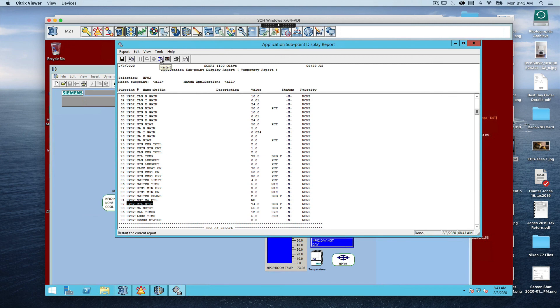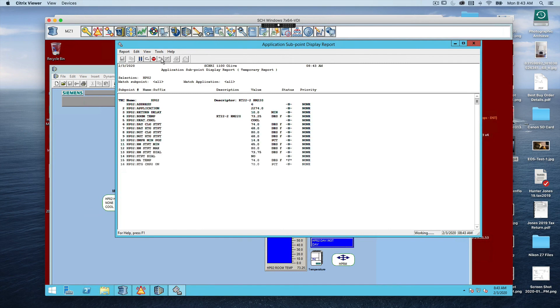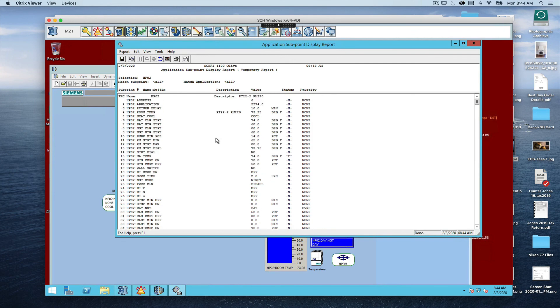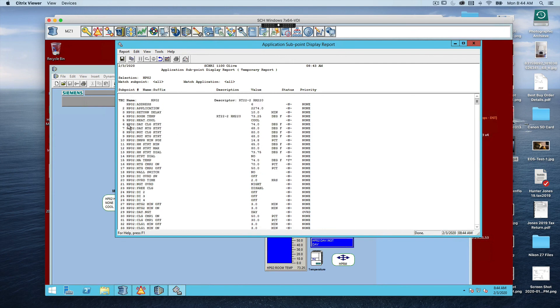Now we'll rerun the report — the blue restart arrow icon runs the report again. We click that, it runs the report, and at point number 92 we can see we've changed the control set point for this heat pump to 73 degrees from 74 degrees. Now it will attempt to control the temperature to 73 degrees. That's pretty much as simple as it gets for changing temperature on a heat pump. Points six and seven — the day and night control set points — control what you call the dead band of the heating and cooling effects.